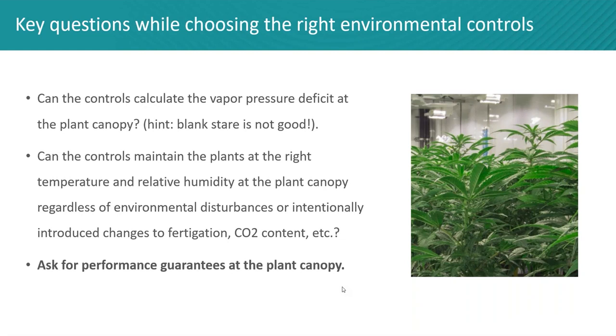Many times we see a control environment where, at implementation, the CO2 dosing isn't actually commissioned for various reasons. Then when it is commissioned, it doesn't tie into the rest of the system - there's no way to measure it other than the sensors themselves, but I can't manipulate the CO2 content. It's critical that you have all manipulated variables at your disposal with the controls, and can bring that information into the control strategy.